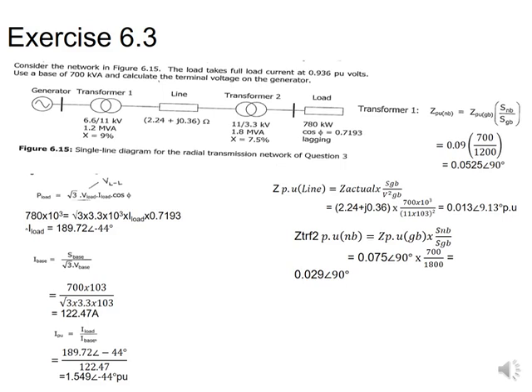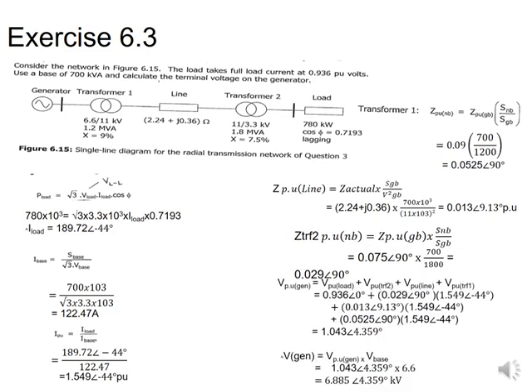Once you have transformer 1, line, and transformer 2 values, you apply the formula for V gen per unit: V load plus V transformer 2 plus V line plus V transformer 1. Remember V load here is 0.936 at 0 degrees. This gives an answer of 1.043 at 4.359 degrees. You then calculate V gen actual as V per unit gen times V base — the voltage closest to the generator is 6.6 kV from transformer 1 — giving a generator terminal voltage of 6.885 kV at 4.359 degrees.